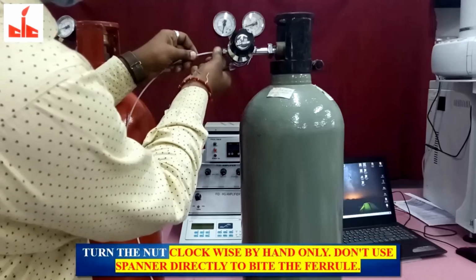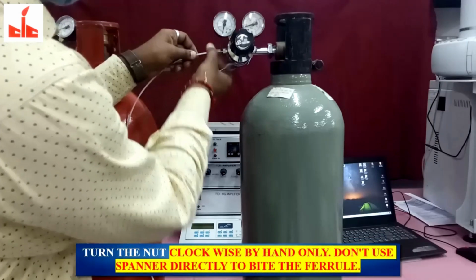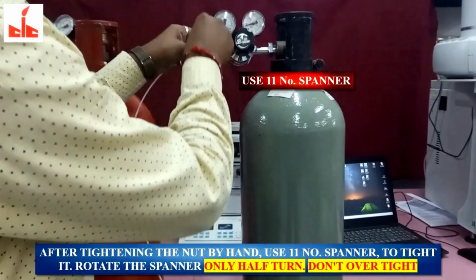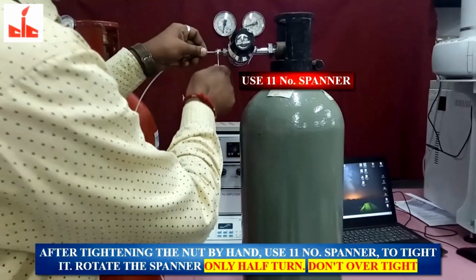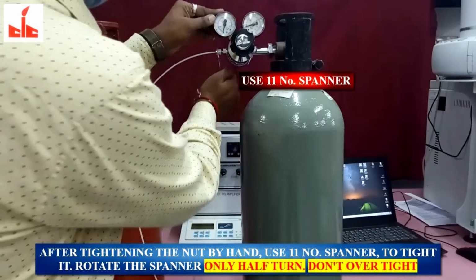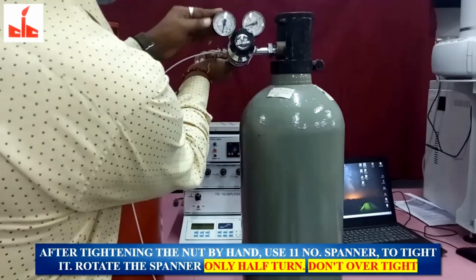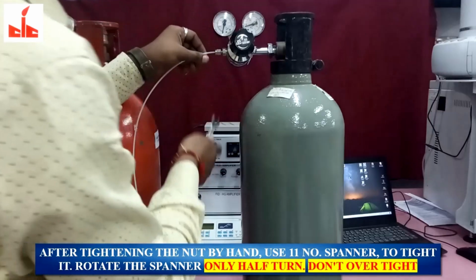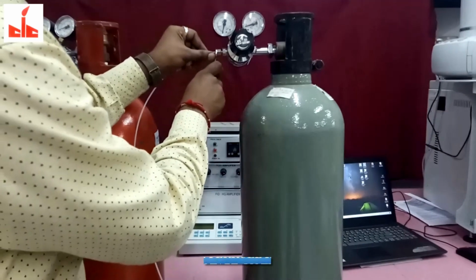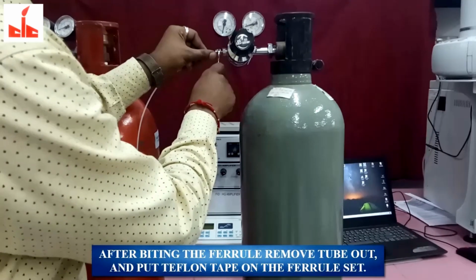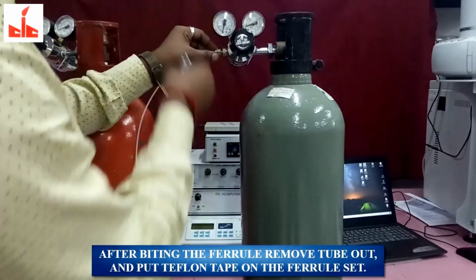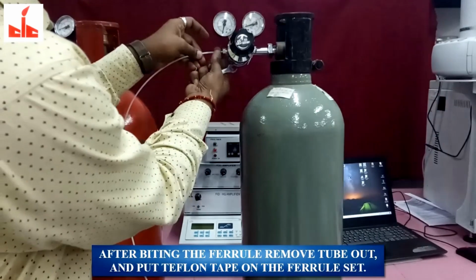Turn the nut clockwise by hand only. Don't use spanner directly to bite the ferrule. After tightening the nut by hand, use 11 number spanner to tighten it. Rotate the spanner only half turn. Don't over tighten it. After biting the ferrule, remove tube out, and put Teflon tape on the ferrule set.